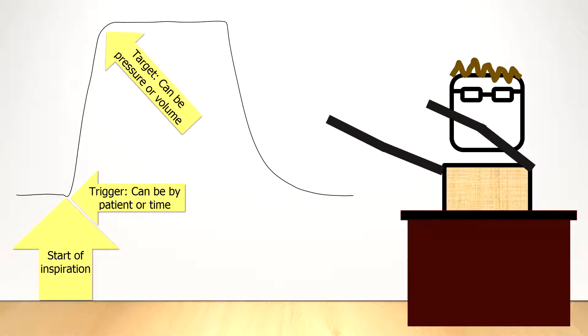Again, I want to remind you that there is a strict relationship between the compliance, the volume, and the pressure in the lungs, and that you have to watch that when you select one variable, such as the pressure, to be the target, then the other variable, volume, is something you have to keep an eye on.